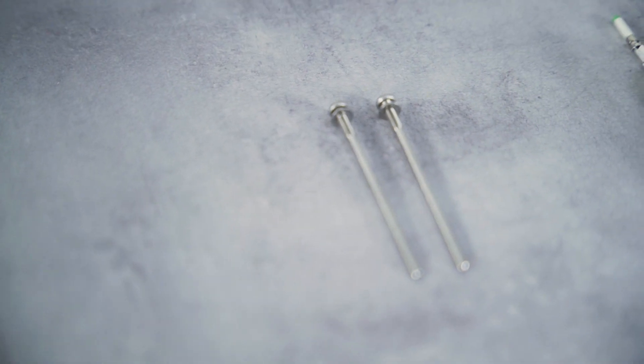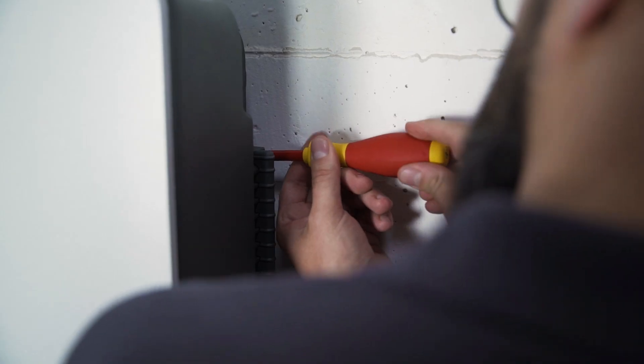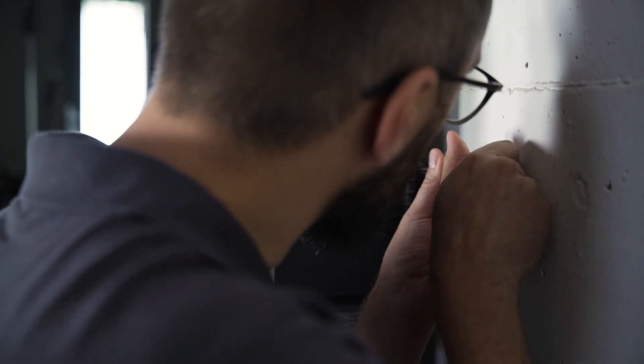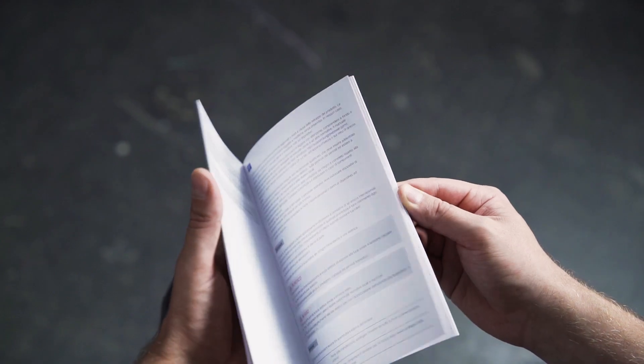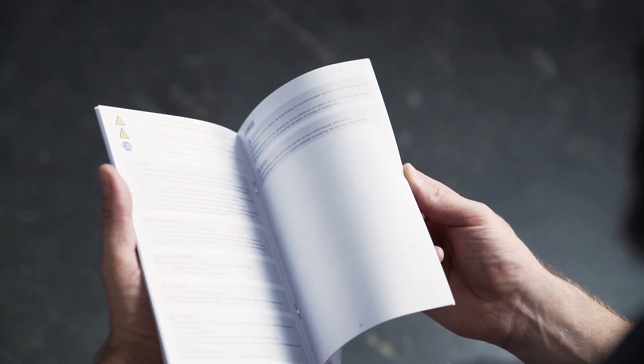For the lift out protection, you need a cross screwdriver to fix the two M4 fixing screws and washers. Before the inverter can be connected, the AC home circuit breaker must be disconnected. The cables must be de-energized and in perfect condition.